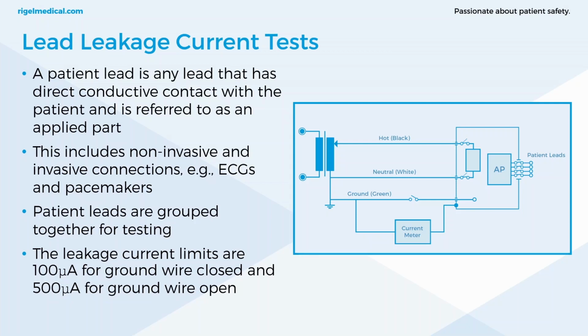So a patient lead is any lead that has direct conductive contact with the patient and is often referred to as an applied part. This includes non-invasive and invasive connections. Now, the manufacturer will specify what is the applied part and what isn't. There'll also be classifications next to where the applied parts connect. This could be ECGs, could be pacemakers. There's all types of devices that it could be.